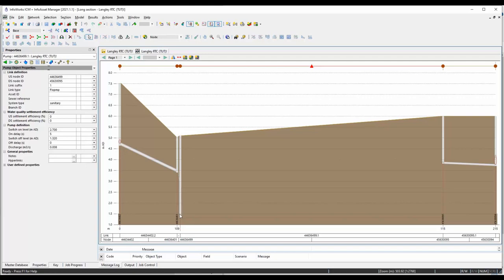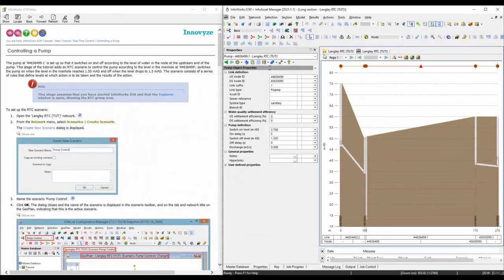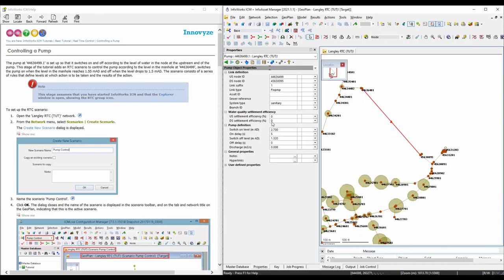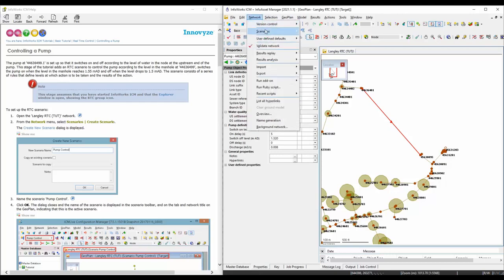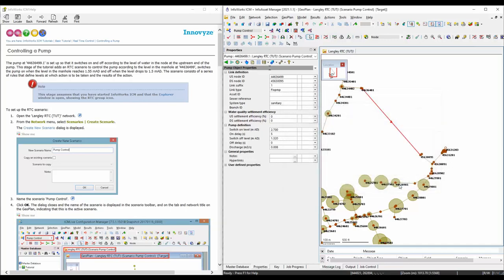What we want to do is turn the pump on at around 1.55 meters and turn it off when the level is less than 1.5 meters. So it will be somewhere around there - remember that's what we're trying to do here. Let's go back to our tutorial. As you can see, we're in the base scenario and we want to create a real-time control rule in a new scenario. Let's go to Network > Scenario > Create a New Scenario and call that 'pump control'.